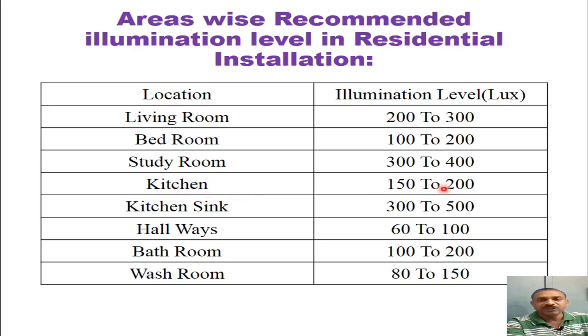The kitchen should have an average illumination in the range of 150 to 200 lux. The kitchen sink, where utensils are to be washed, should have an illumination level of 300 to 500 lux. The hallways in a residential building should have an illumination level of 60 to 100 lux. The bathroom should have 100 to 200 lux, and the washroom should have an average illumination level of 80 to 150 lux.